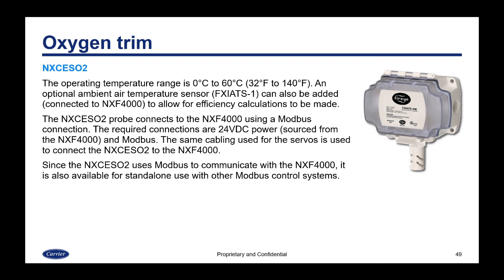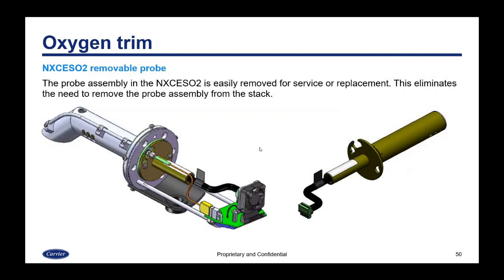The NXCESO2 probe connects to the NXF4000 using a Modbus connection. The required connections are 24 volts DC power, which is sourced from the NXF4000, as well as the Modbus cable connection. The same cabling used for the servos is used to connect the NXCESO2 to the NXF4000. Since the NXCESO2 uses Modbus to communicate with the NXF4000, it is also available for standalone use with other Modbus control systems. With the NXCESO2, the probe assembly is easily removed for service or replacement, and this would eliminate the need to remove the probe assembly from the stack itself.